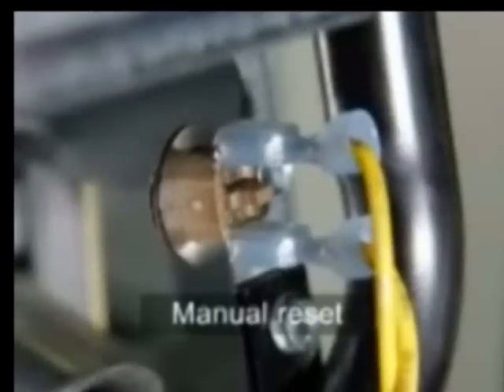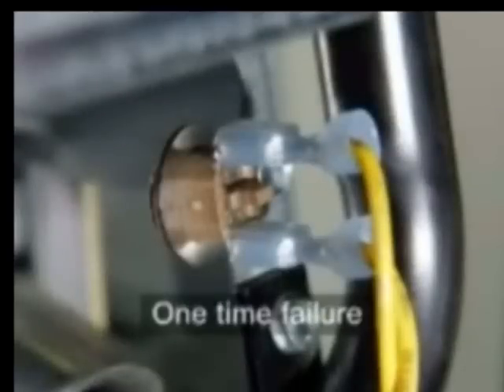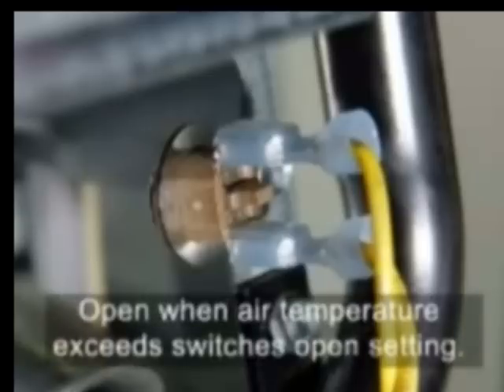These limit switches are 24-volt operated manual reset or one-time failure devices that open when the air temperature they sense exceeds the switch's open setting.